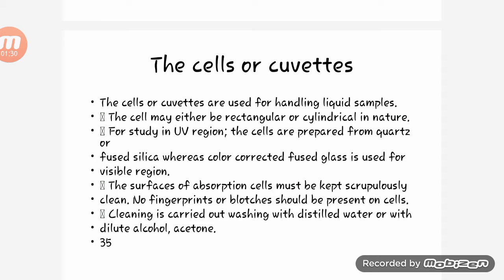The surface of the absorption cell must be kept scrupulously clean. No fingerprints or blotches should be present on the cell. Cleaning is carried out by washing with distilled water or with dilute alcohol or acetone.